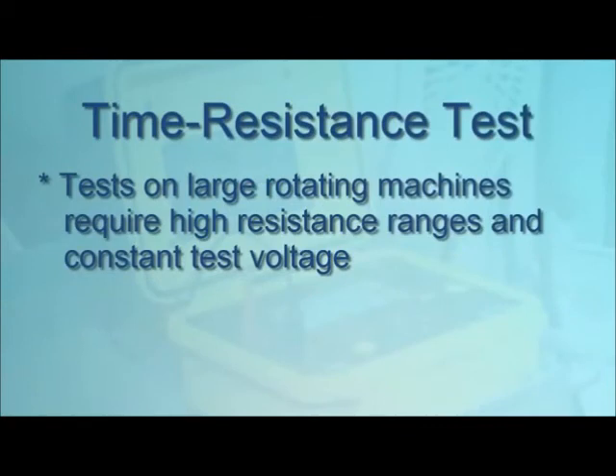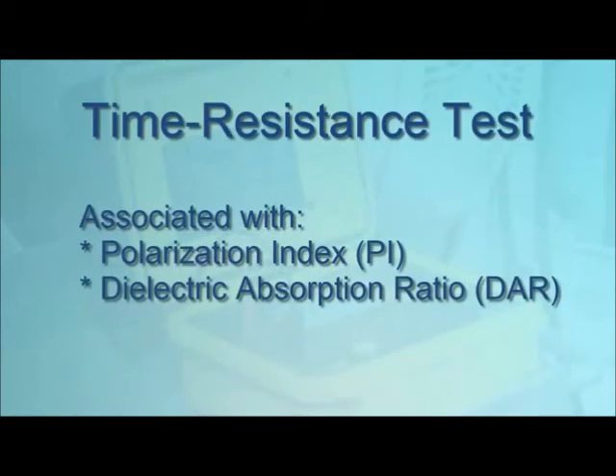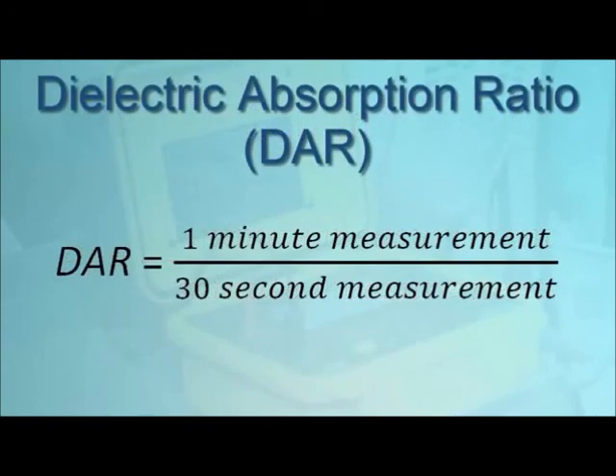Time resistance tests on large rotating electrical machinery, especially systems at high operating voltage, require high insulation resistance ranges and a very constant test voltage. Since this test provides meaningful results within a single 10-minute duration, it is relatively independent of temperature and independent of the size of the system under test. The time resistance test is sometimes associated with two values: the polarization index, or PI, and the dielectric absorption ratio, or DAR. The PI is derived by dividing the 10-minute resistance measurement by the 1-minute measurement. The DAR is calculated by dividing the 1-minute measurement by the 30-second measurement. Although DAR is no longer commonly used with new insulation systems, it may still have applicability when testing older insulating materials.